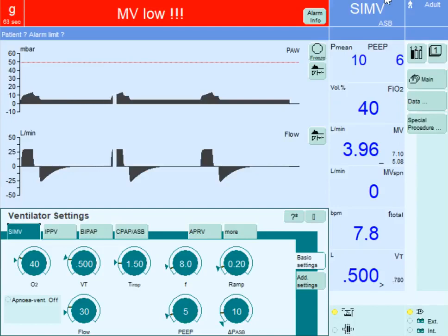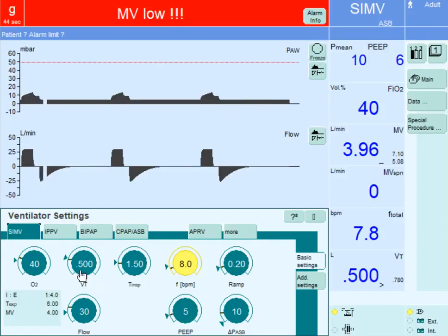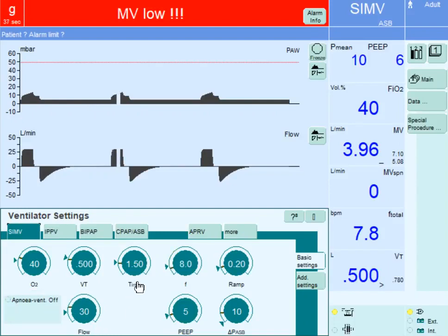In Synchronized Intermittent Mandatory Ventilation, SIMV, the ventilator settings include FiO2 at 40%. The target or control is a tidal volume of 500 ml, delivered with a flow rate of 30 liters per minute. The inspiratory time is set at 1.5 seconds, which is the cycling mechanism in this mode.